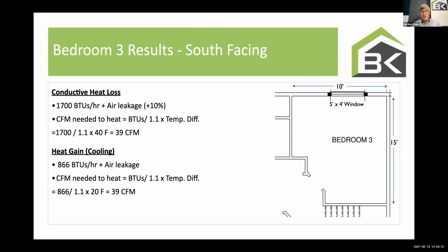Except F280 now says the bedroom on the 3rd floor actually doesn't have a lot of air leakage because it's above the neutral pressure plane. So I'm going to say to you, on average, this isn't exactly true, but you'll get the idea. They apportion the air leakage. We don't know the air leakage of bedroom number 3, so what do we do? We kind of guess, and we estimate. And we say it's roughly 10% of the heat loss of the house, so 1,700 BTUs plus 10% is kind of what it would say.